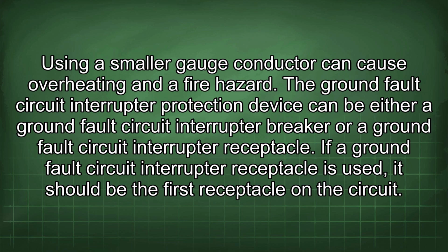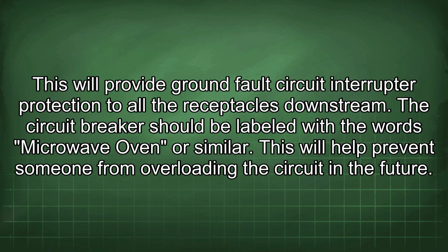The ground fault circuit interrupter protection device can be either a ground fault circuit interrupter breaker or a ground fault circuit interrupter receptacle. If a ground fault circuit interrupter receptacle is used, it should be the first receptacle in the circuit. This will provide ground fault circuit interrupter protection to all the receptacles downstream. The circuit breaker should be labeled with the words microwave oven or similar. This will help prevent someone from overloading the circuit in the future.